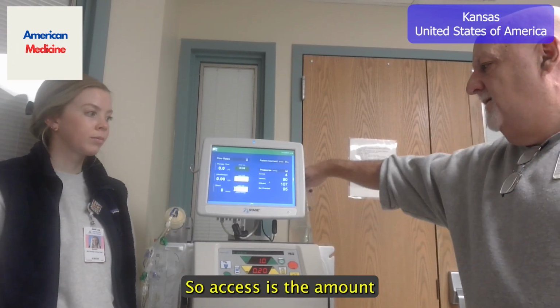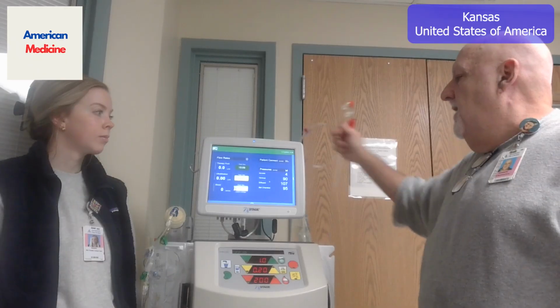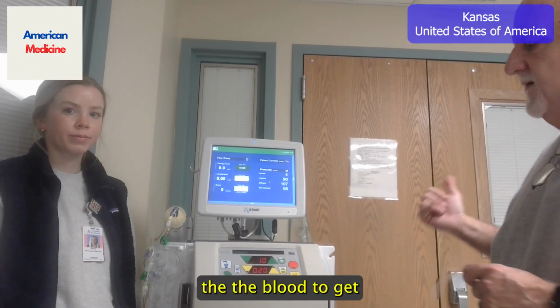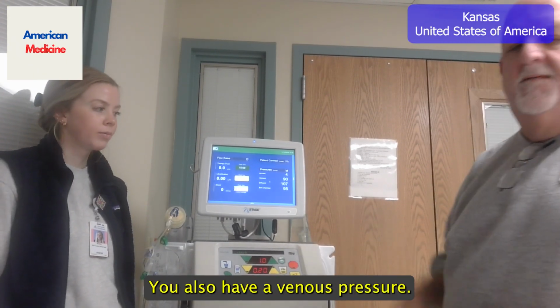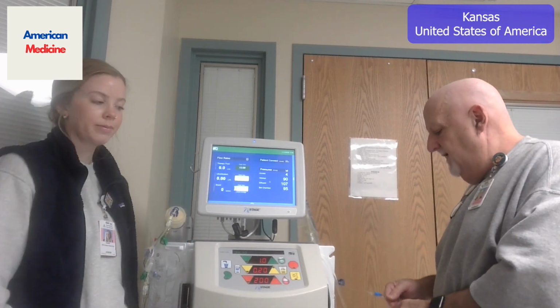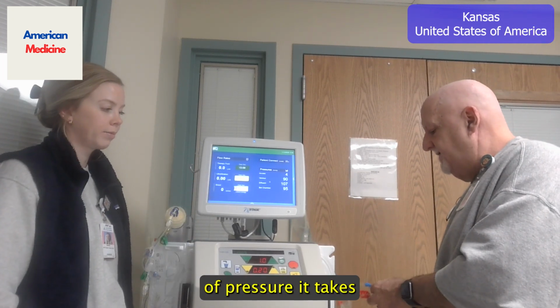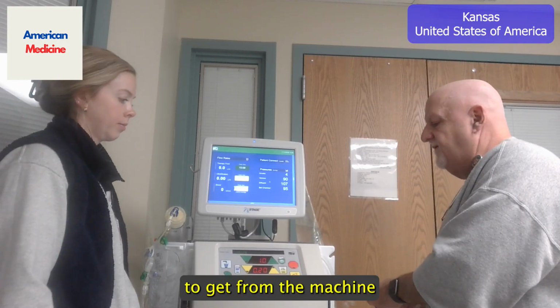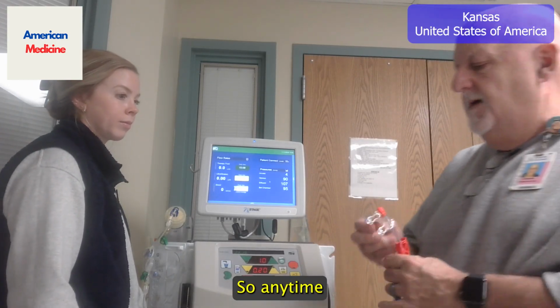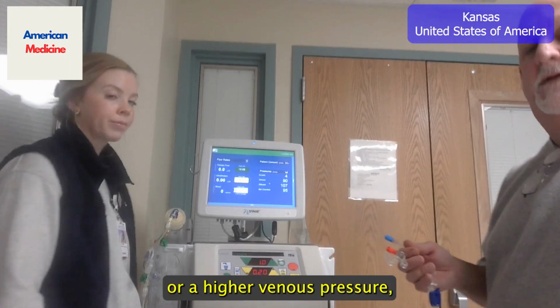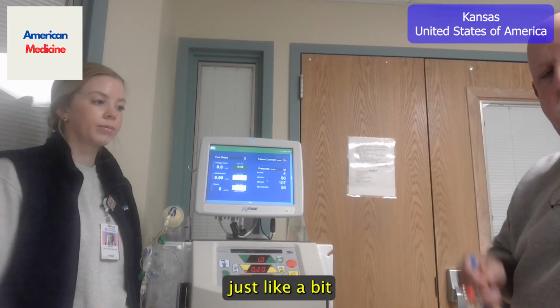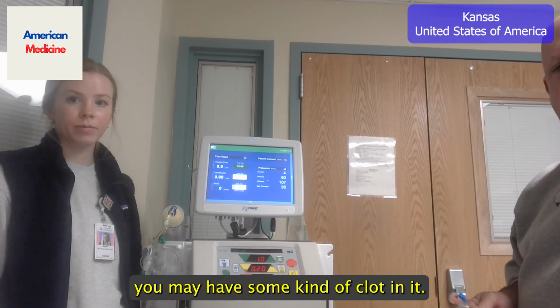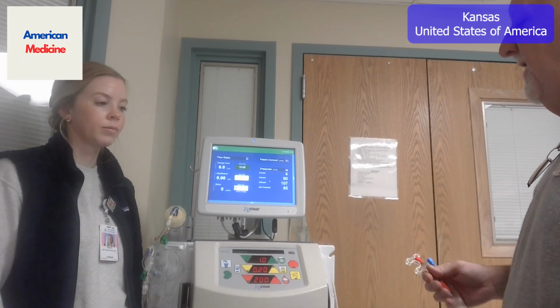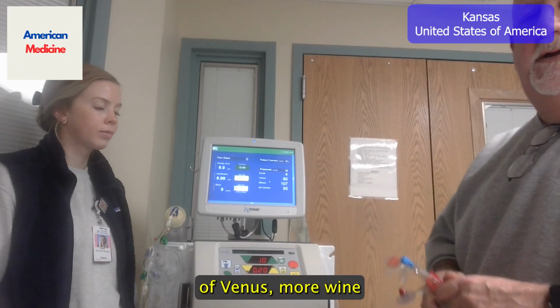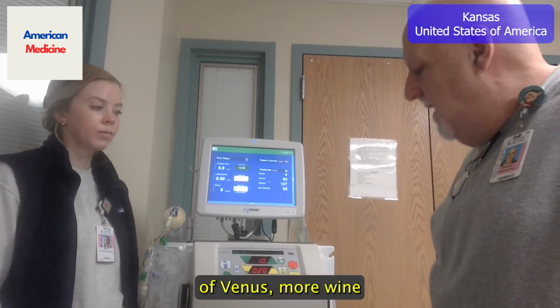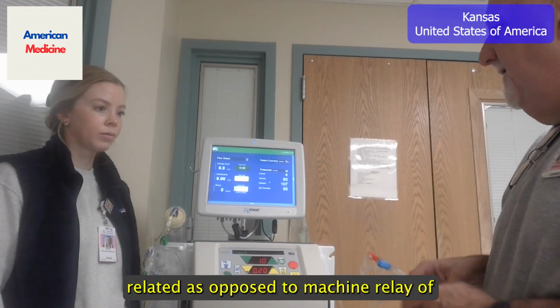So access is the amount of pressure it takes for the blood to get from the patient to the machine itself. You also have a venous pressure. The venous pressure is the amount of pressure it takes to get from the machine back to the patient. So anytime you have a low venous pressure or a higher venous pressure, once again, just think of it like your arterial line. You may have some kind of clot in it, or you could be sluggish at that point. So anytime we start getting access or venous, it's more line related as opposed to machine related.